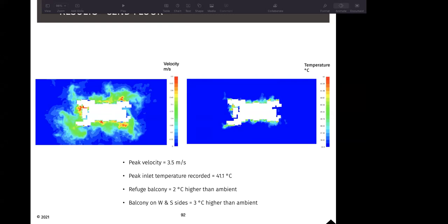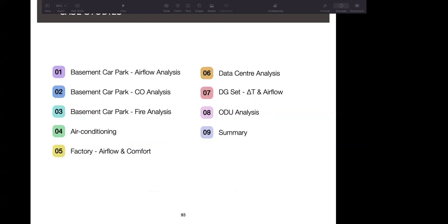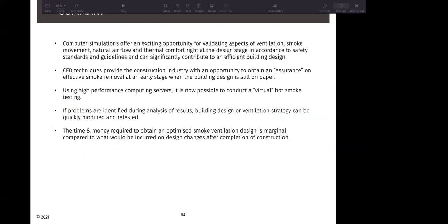So for an ambient of 35.9 degrees centigrade, we have a peak inlet temperature recorded of 41 degrees. There is a rise of 6 degrees just because of the thermal stacking. So depending on that, we can study whether there would be any derating of ODUs within the system, and whether this inlet temperature is exceeding the acceptance criteria. So those were all the case studies.